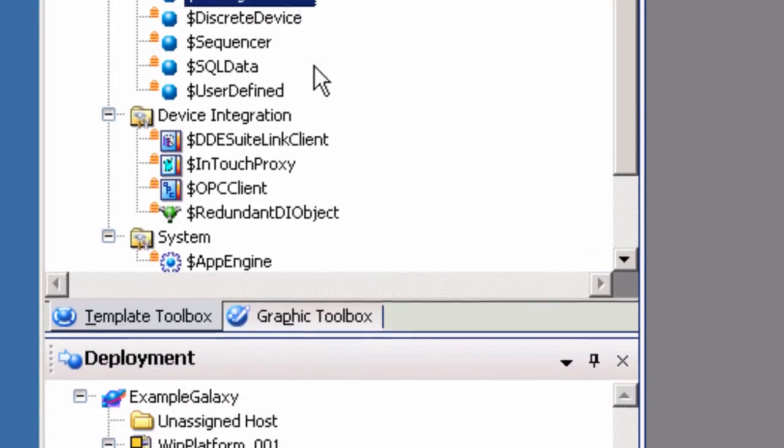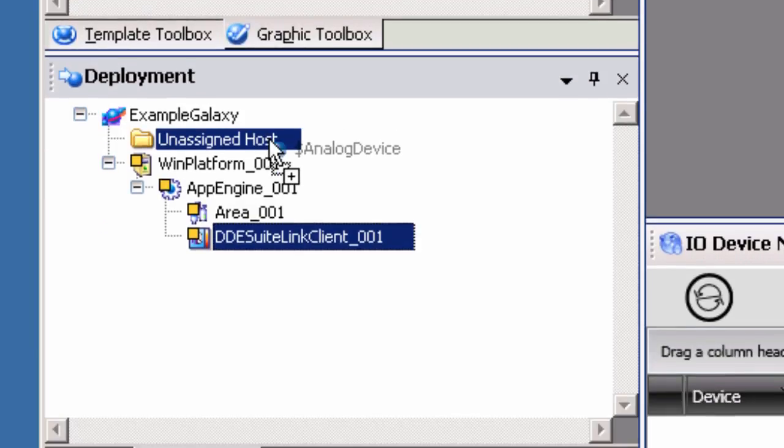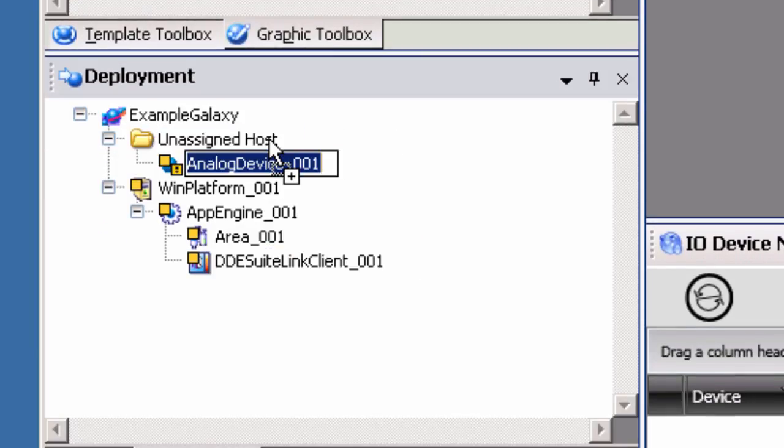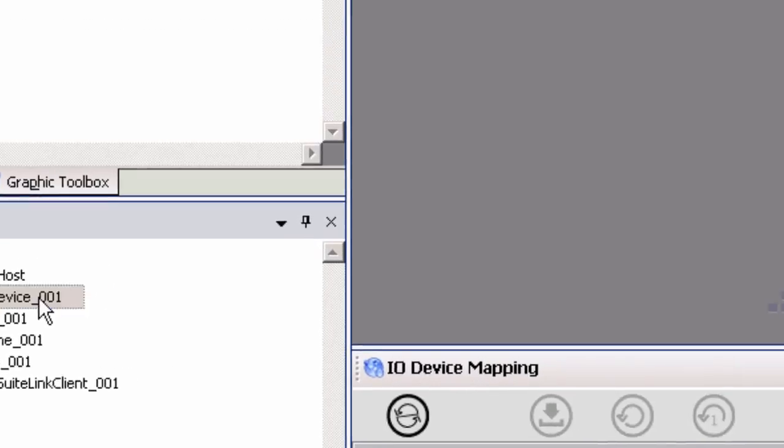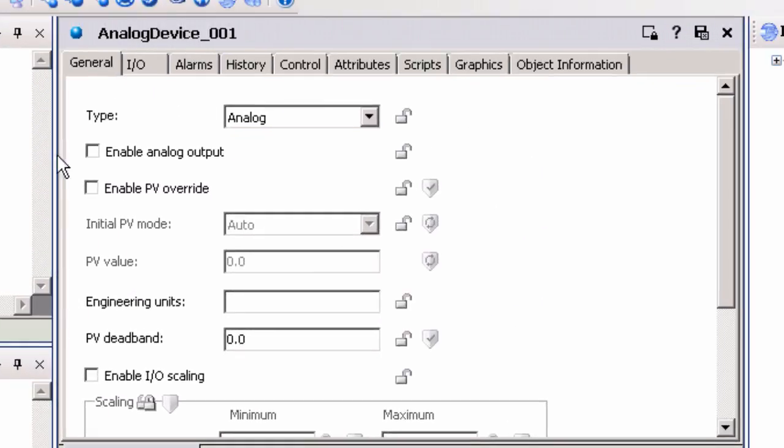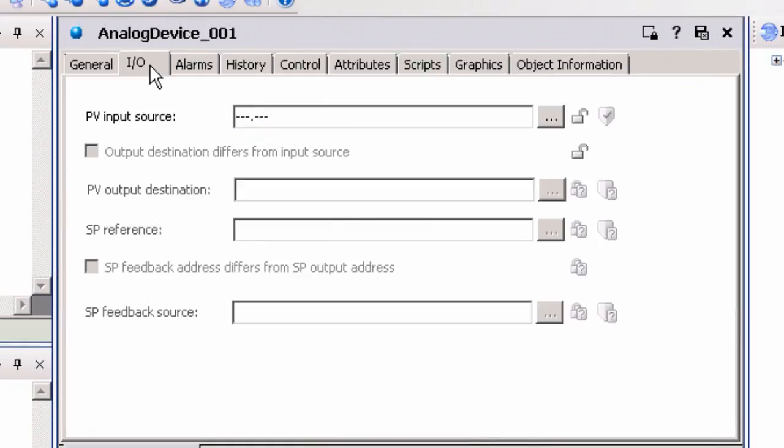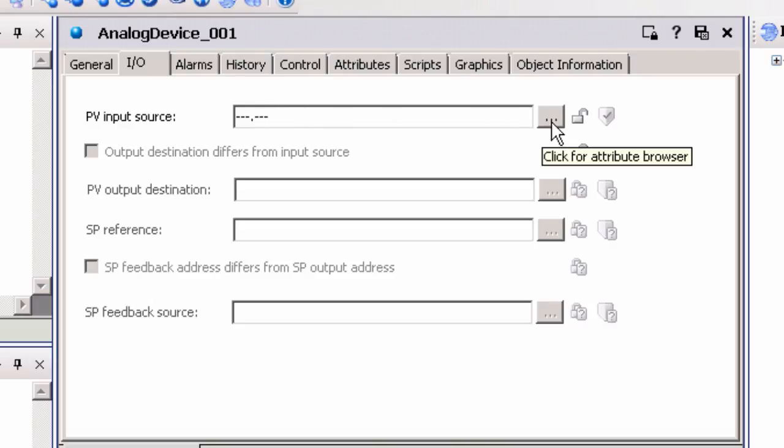Drag and drop the Analog Device Application Object under the Unassigned Host folder. Double-click the Analog Device Object to open the Properties dialog. An item must be assigned to the object. This assignment is made by entering the full path, including the Topic Name and Item Name, in the PV Input Source field.